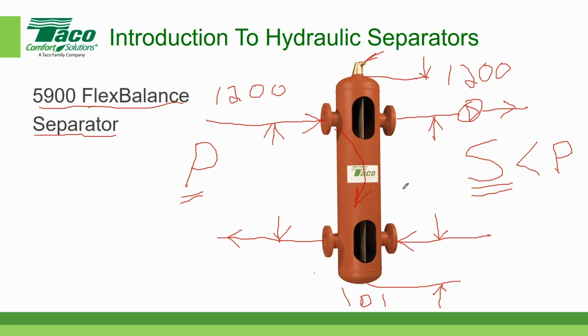Any questions about the first pre-engineered component? There's a nice question/comment. I've worked on some projects where there's been some issues with the bridge or separation, the primary secondary loop. So if I use this component here, I shouldn't have any issues on any more of my projects, correct? That's correct. And what you have to make sure is that it's sized properly. We will get into the sizing in a moment. So as long as it's sized properly and the piping is done properly, then it takes all the guesswork out.